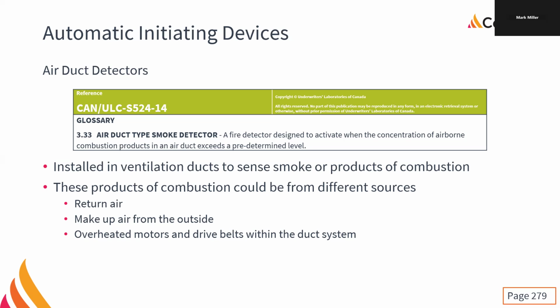That smoke could be coming from different sources. It could be coming from the return air. It could be coming from makeup air from the outside, or it could be coming from inside the air handling unit, the actual overheated motors and drive belts. Those are the three locations we could be getting it from.